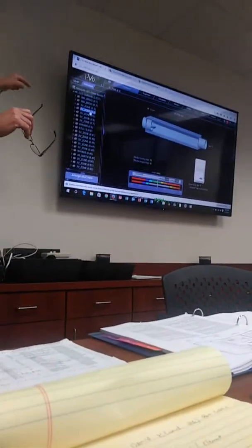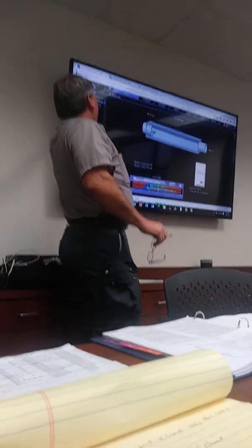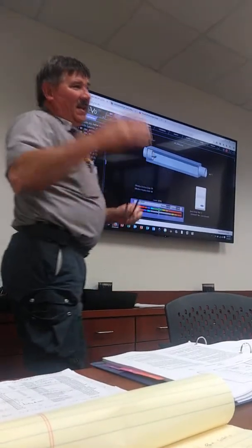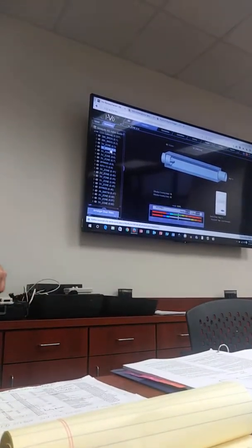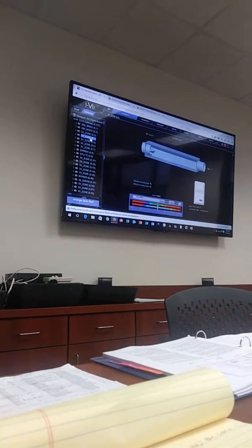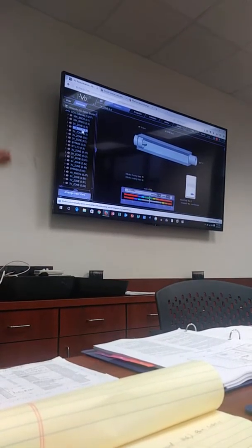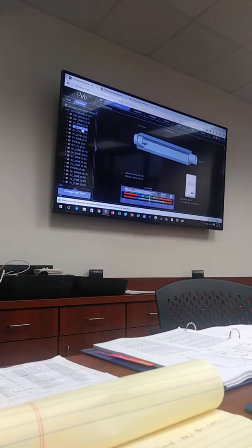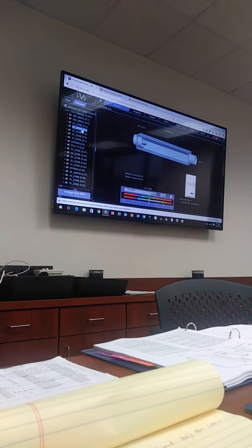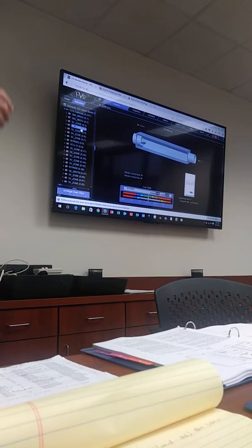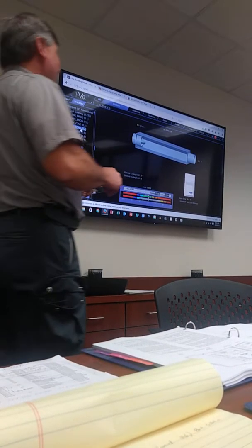The reason it's on the inlet side is if this guy wants cooling, he's looking at that temperature sensor that's on the inlet side of the damper, you know, it's behind the door here. And it's going to say, okay, you want cooling, but the air on the other side of this door is 90 degrees. So even though you want it, we're not going to open the door, because then we're just going to make it worse. But it's got a minimum.